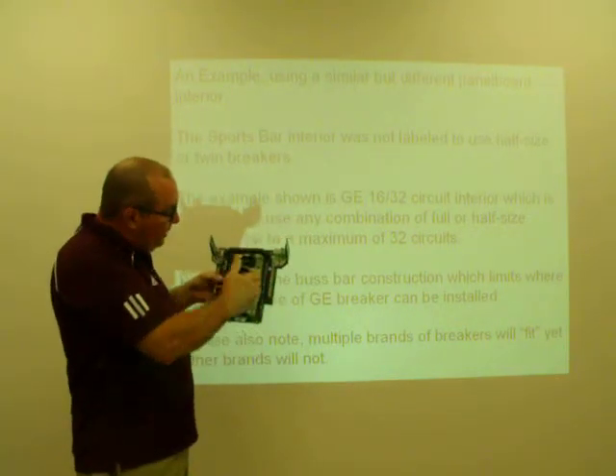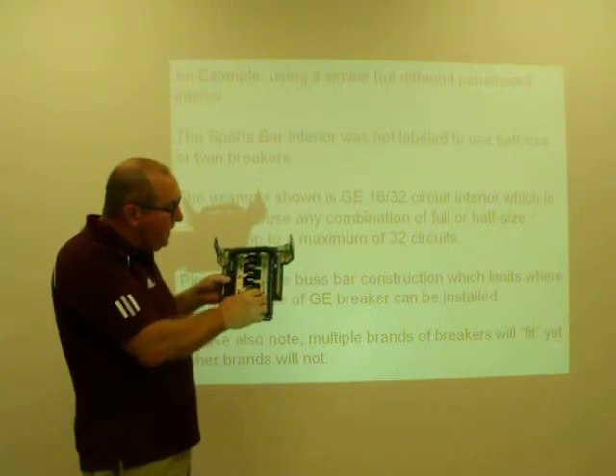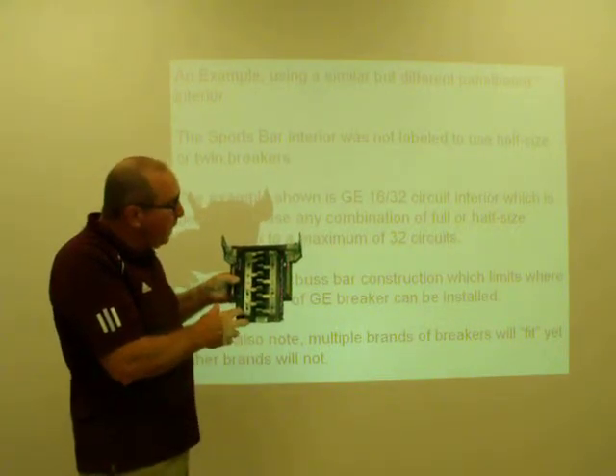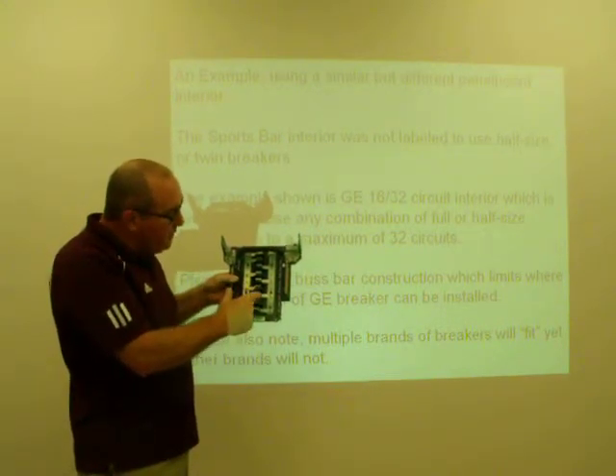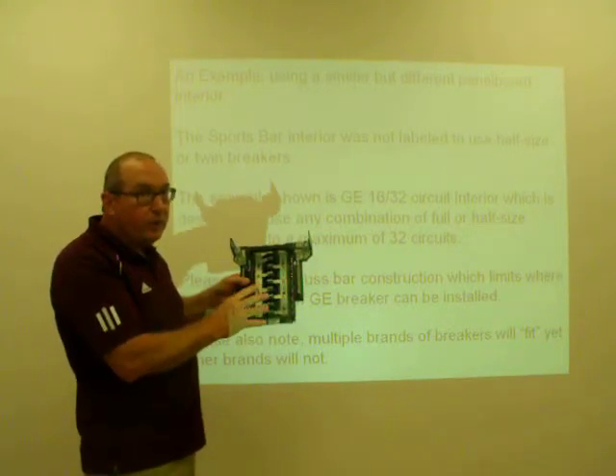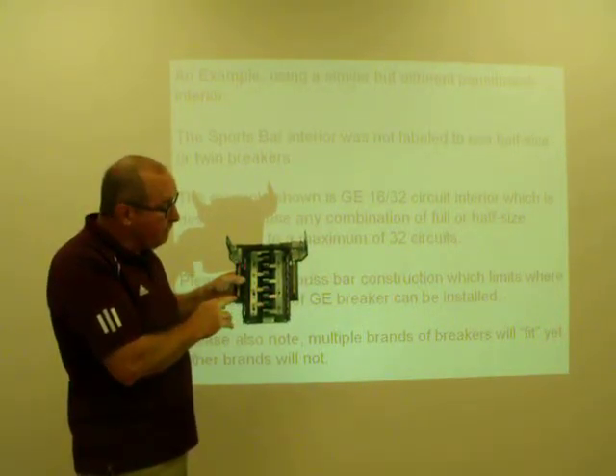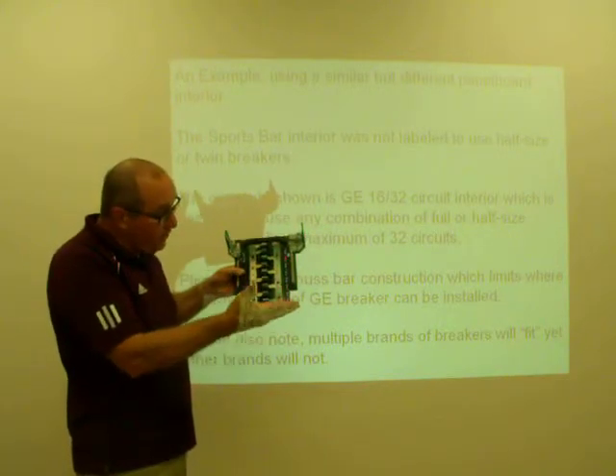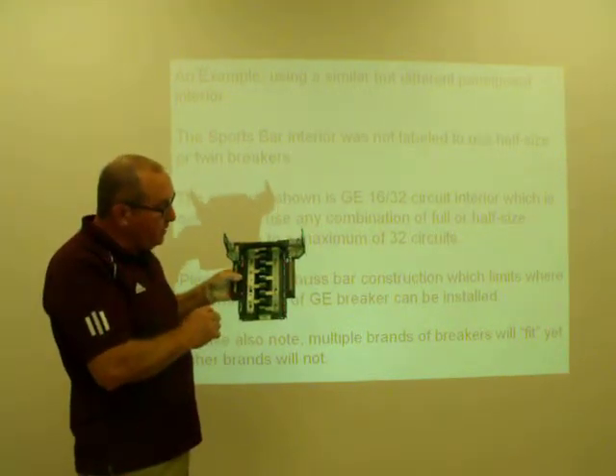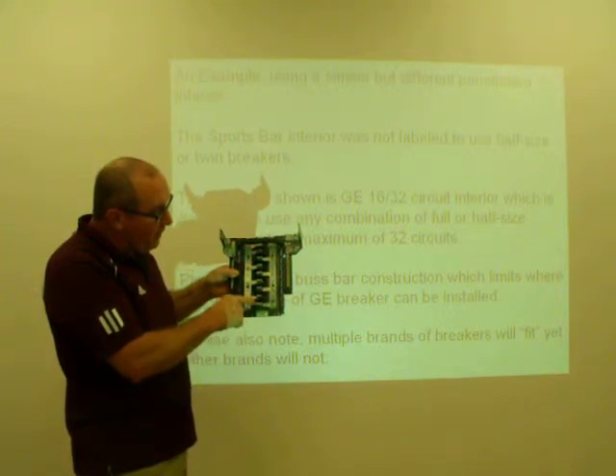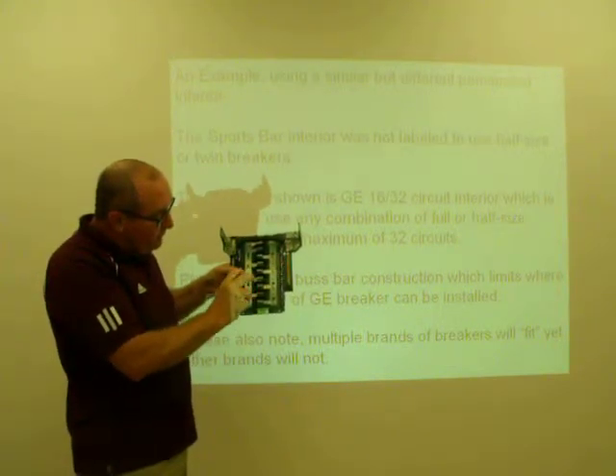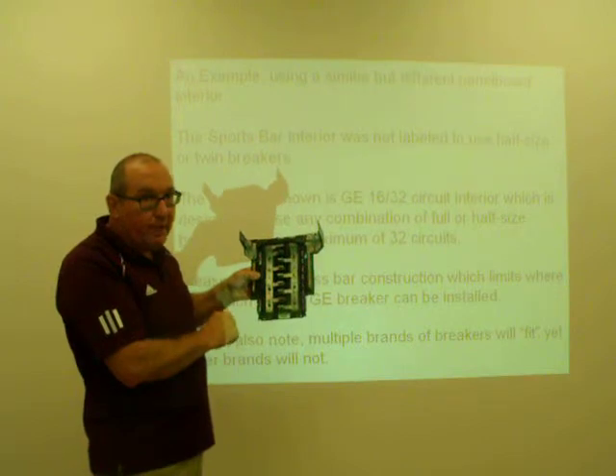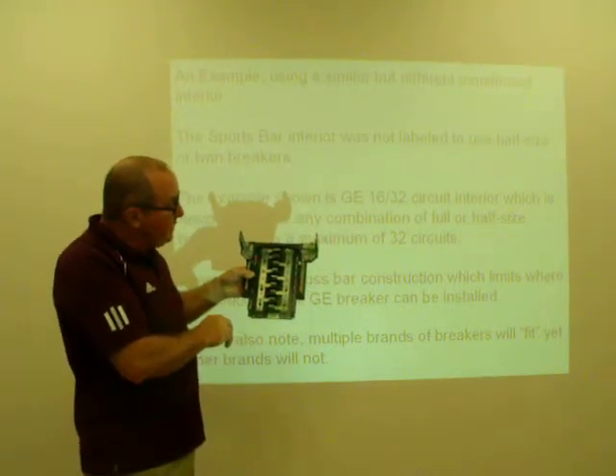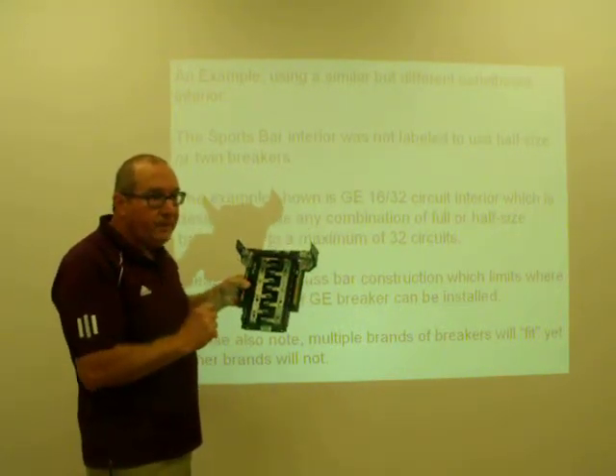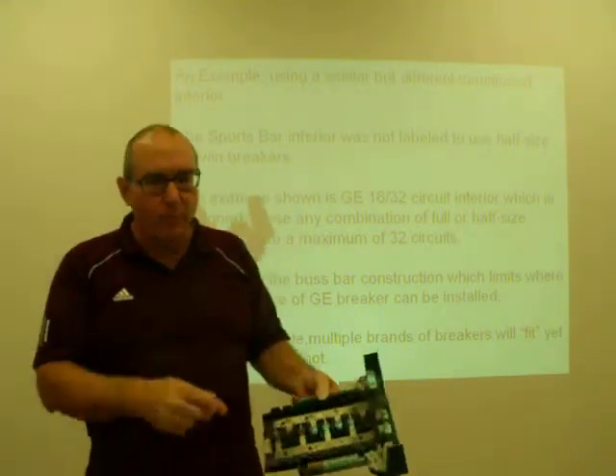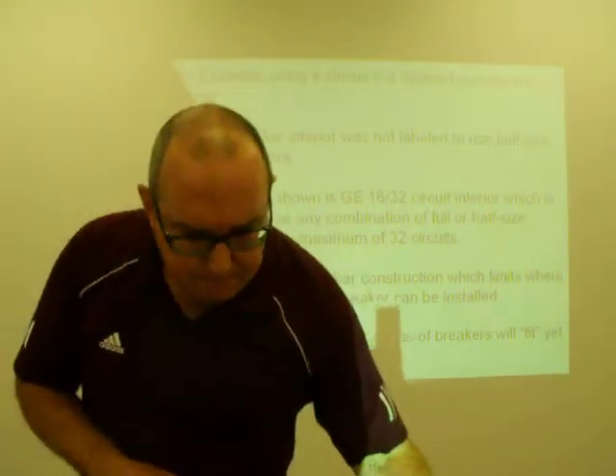and this interior is designed to hold 16 full-size breakers, or up to 32 half-size breakers. Every spot in here is capable of holding 2 half-size breakers, or somewhere between 16 and 32, however you want to configure it. A typical GE panel board will simply have this large tab here without these additional notches that help support the half-size breakers. And then some breakers will have physical restrictions on the bottom of them that will prevent you from installing them in the wrong spot.